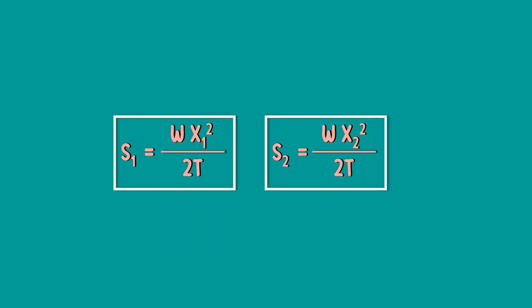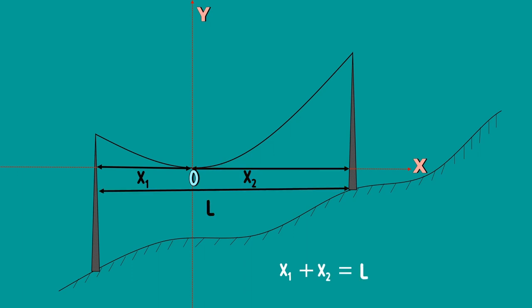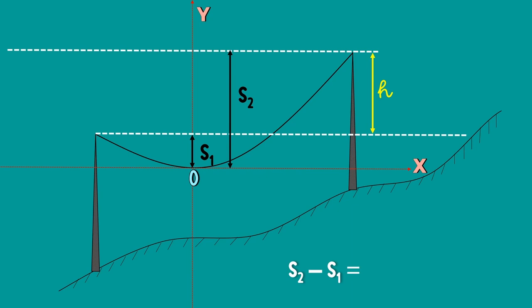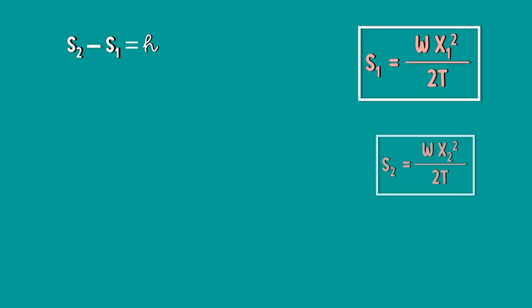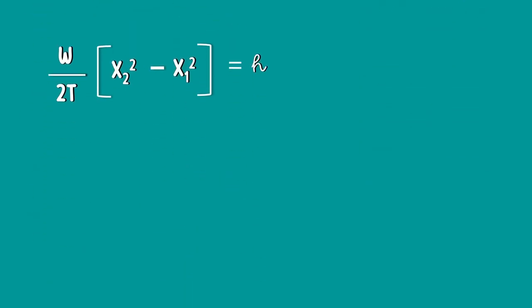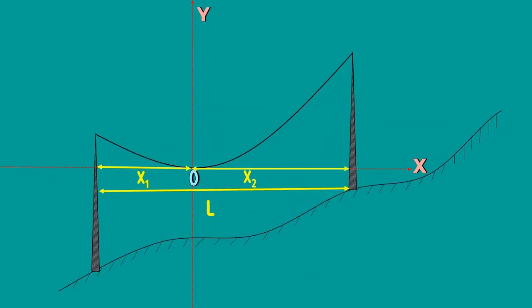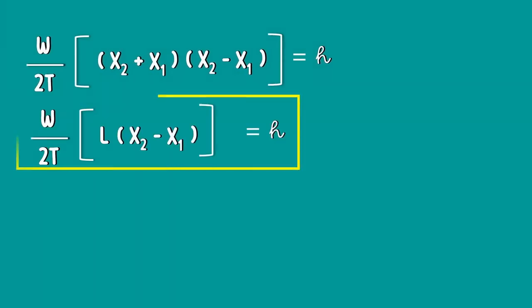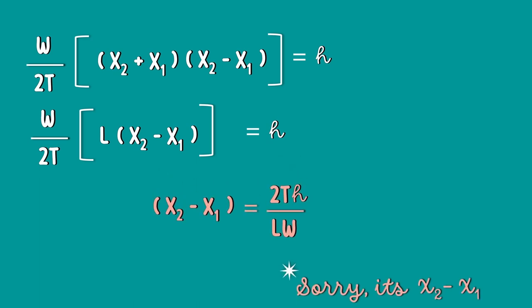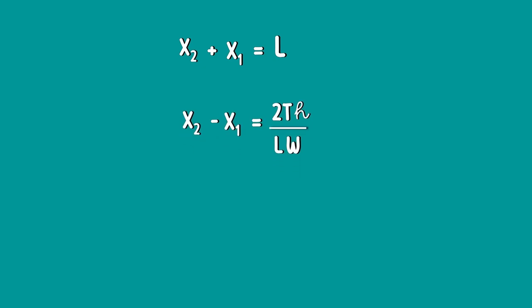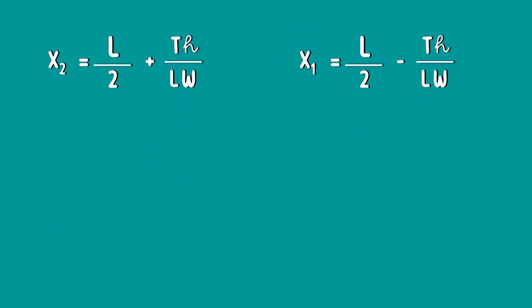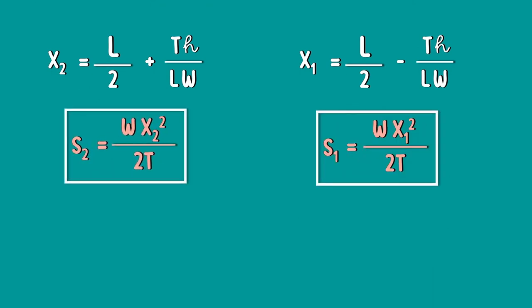In these two sag equations, the values X1 and X2 are unknown. We need these two values to find the exact value of the sags. We know that X1 plus X2 is the span L and S2 minus S1 is the difference in levels between two supports H. Let's substitute our S1 and S2 values in this equation. We know that X2 square minus X1 square can be written as X2 plus X1 into X2 minus X1. By substituting the X2 plus X1 value as L, we will get our equation for H. From here, we can find X2 minus X1. Now we have X2 plus X1 equation and X2 minus X1 equation. We can get our X2 and X1 values by solving these two equations. Once you know these values, the sags S1 and S2 can be calculated easily.